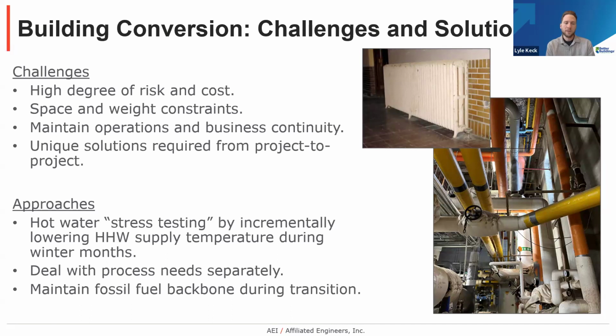So the outcome of this stress testing is to affirm design conditions as well as focus the scope of the building conversion project so that it's feasible, cost effective and practical. A few other approaches involve dealing with process needs separately. Many existing buildings with high grade heat sources serve all of the needs in the building off of that source. So look to decant some of those process or specialty needs off of your main system and make sure that you're not over designing, avoiding the tail wagging the dog type of scenario. And so deal with process needs separately. And additionally, maintaining a fossil fuel backbone during the transition is a very common practice as well. Next slide, please.